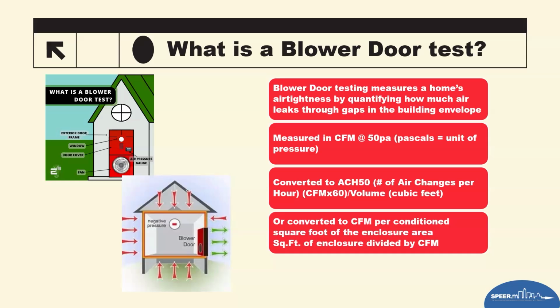For example, an 800 square foot apartment can roughly test out, if you did the calculation, at a 6 or 7 ACH or possibly higher, as long as it's below that 0.30 or 0.27 CFM per conditioned floor area respectively, and that's due to changes in the code. So that helps with smaller buildings. And if you're in a city that's still on the 18 and you've got rental property being built, or just smaller homes in low-income housing, let's say 1,100 or 1,200 square feet, they're decent, but they're small homes.